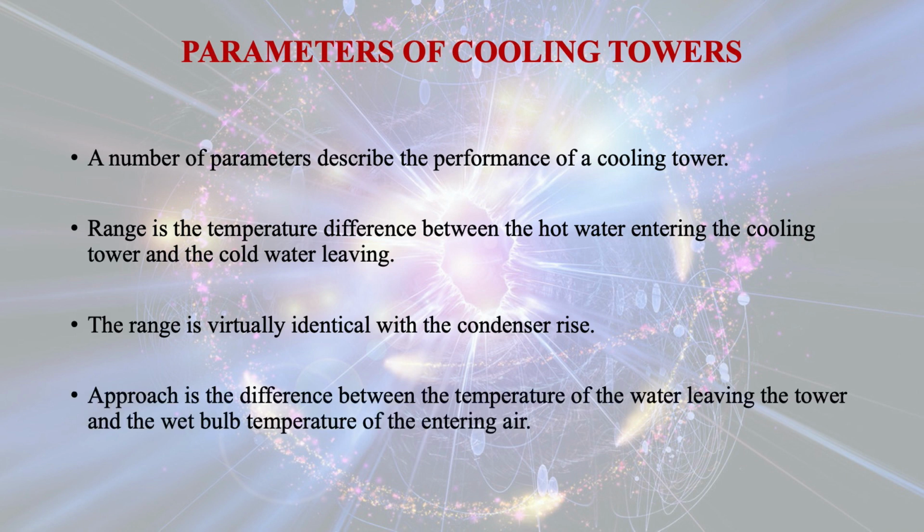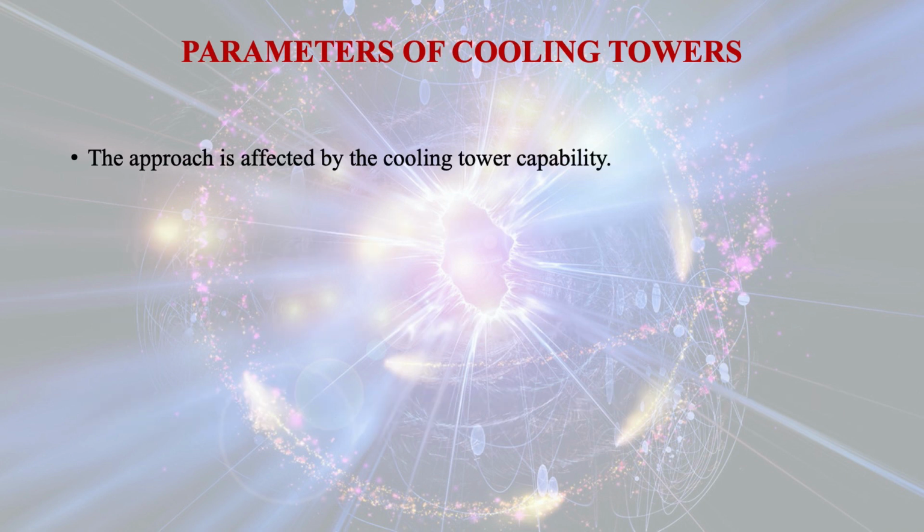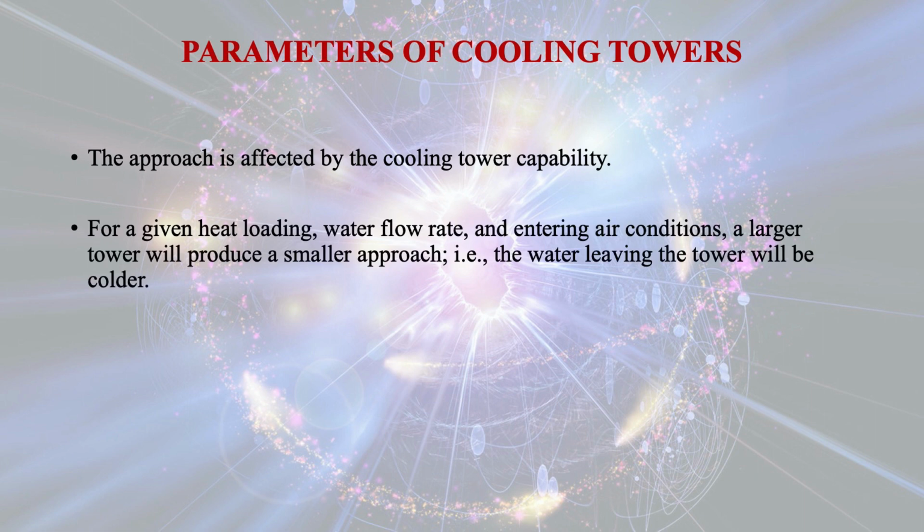Approach is the difference between the temperature of the water leaving the tower and the wet bulb temperature of the entering air. The approach is affected by the cooling tower capability. For a given heat loading, water flow rate and the entering air conditions, a larger tower will produce a smaller approach. The water leaving the tower will be colder.